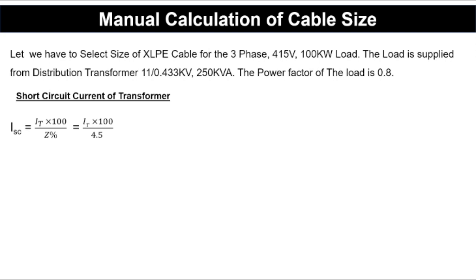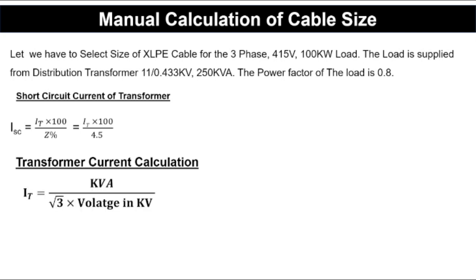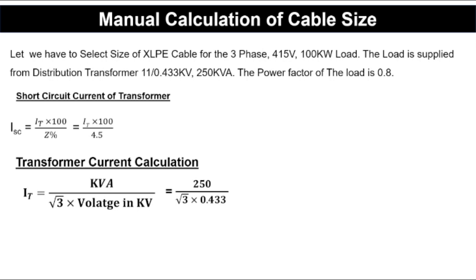To calculate the short circuit current, we first find the transformer's current rating. IT = kVA rating / (√3 × voltage in kV) = 250 / (√3 × 0.433) = 333.34 amperes. Putting this into the short circuit current equation: ISC = 333.34 × 100 / 4.5 = 7407.56 amperes, that is 7.407 kilo-amperes.